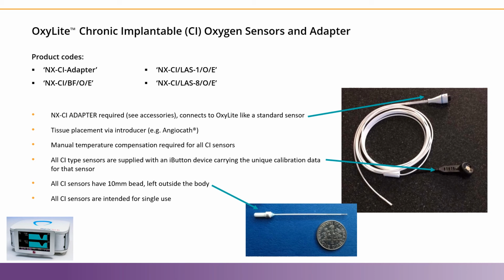All of the CI sensors require the use of the CI adapter, seen here on the right. It has a standard OxyLite sensor connector with a blue ring that matches the OxyLite system, and connects like all the other standard probes. All CI sensors are provided with an I-button device that carries the calibration info of the sensor.